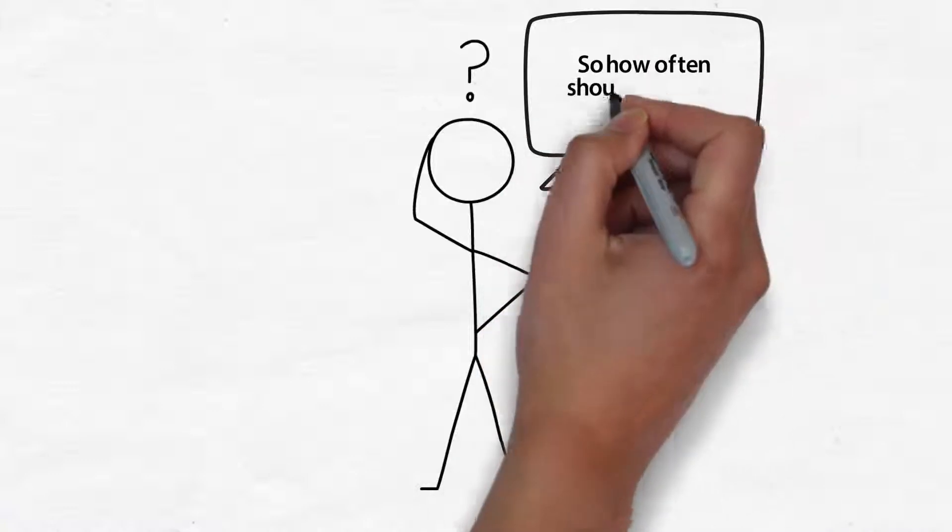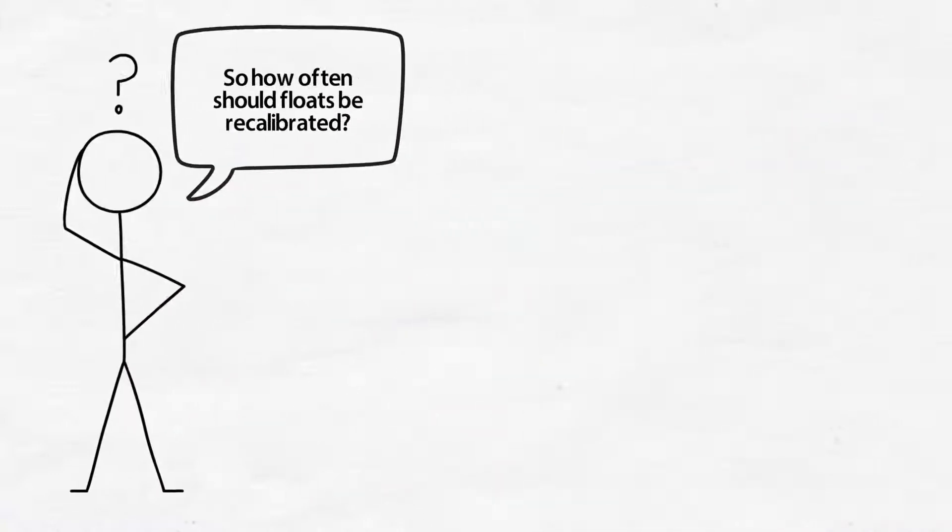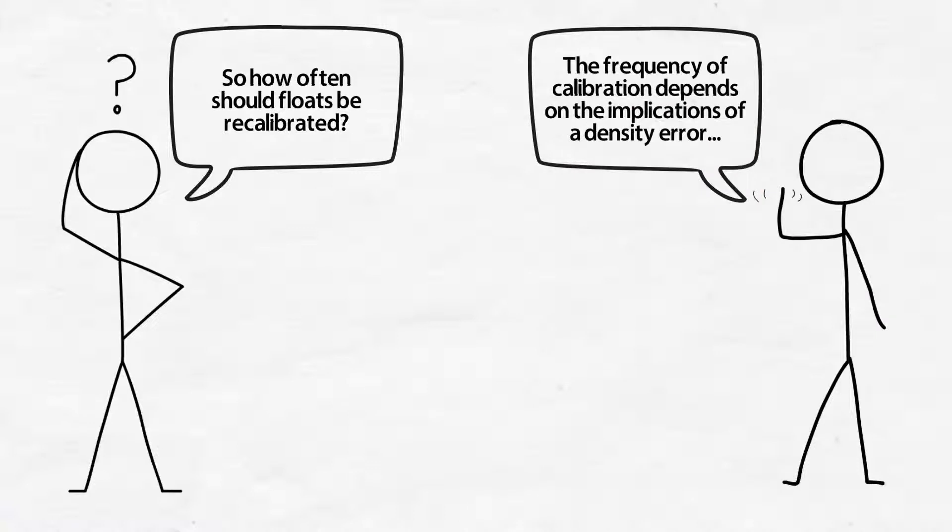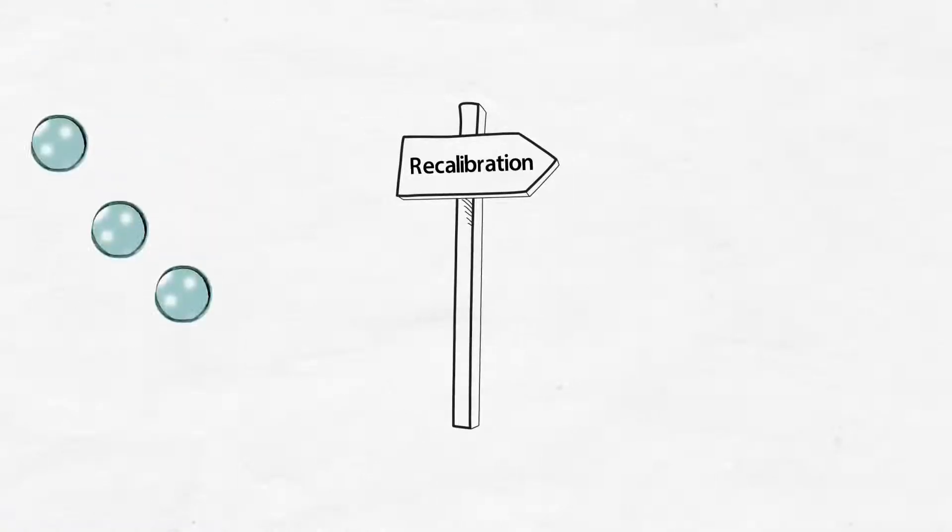How often should floats be recalibrated? Ultimately, the frequency of calibration depends on the implications of a density error. In order to maintain accurate results, floats must be recalibrated if you suspect they have been dropped, abraded, or suffered any other damage.